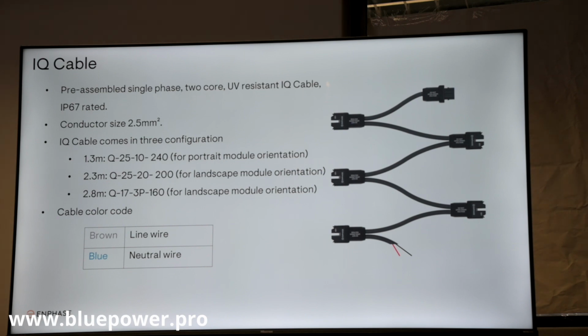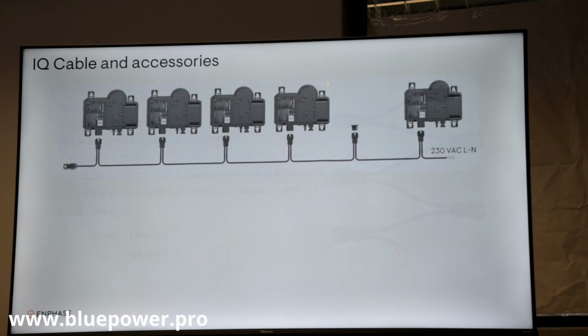You'll find that the live on the installation is blue, and then you've got black, grey, I can't remember the other color. In any case, our 3-phase cable color coding does not align, and we've actually had someone make a mistake that damaged microinverters because of that. So watch out when you install a 3-phase system using these cables.